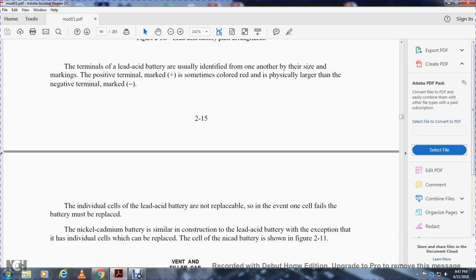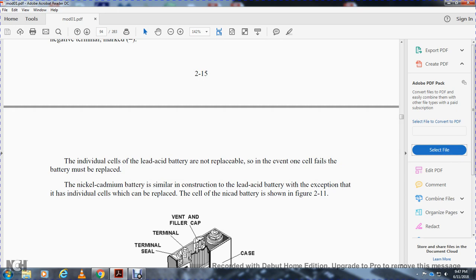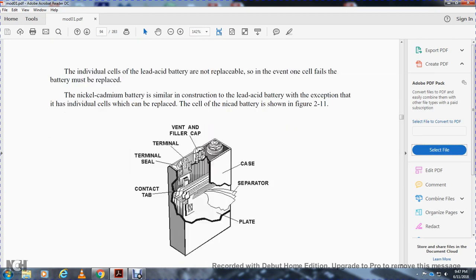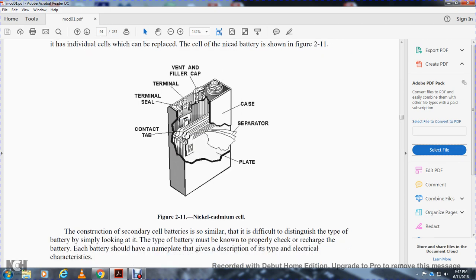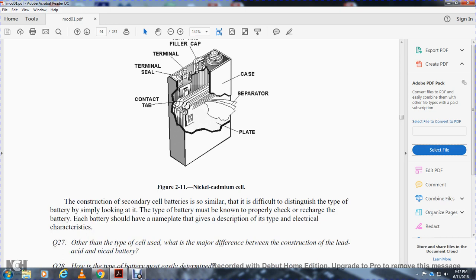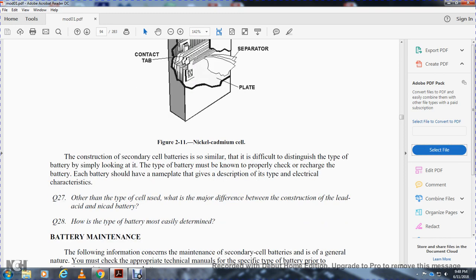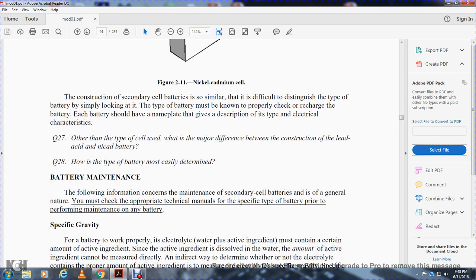Lead acid batteries are identified by markings; the positive terminal is marked with a plus sign, sometimes colored red, and is physically larger than the negative terminal marked with a minus sign. Individual cells in lead acid batteries are not replaceable; if one cell fails the entire battery must be replaced. The nickel cadmium battery is similar in construction to the lead acid battery, with the exception that it has individual cells that can be replaced. Each battery should have a nameplate giving the description, type, and electrical characteristics. The major construction difference between lead acid and nickel cadmium batteries is that nickel cadmium cells are individually replaceable.